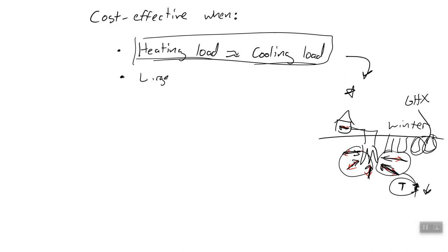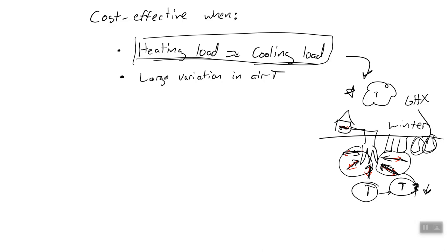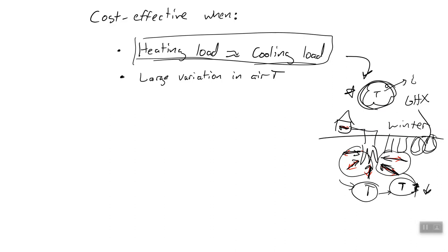These are also great if you have a large variation in air temperature. The true utility of a ground source heat pump is that we're connected to the ground, which is at more or less a constant temperature, although, like we said, it might change very slowly over time. Whereas the air outside, where an air source heat pump is operating, could change drastically. If it's changing drastically, you're going to see a wide array of COPs, and it's hard to size your heat pump correctly and optimally. So if you see a large variation in these outside temperatures, it's good to use the very constant ground temperature. But if your air temperature is essentially the same with time, if there is really no change with time, then you might as well use the air instead of the ground and save some money.